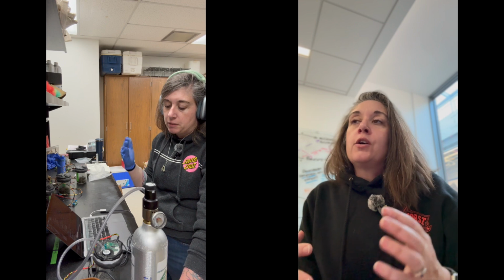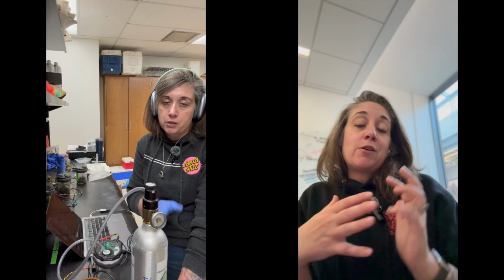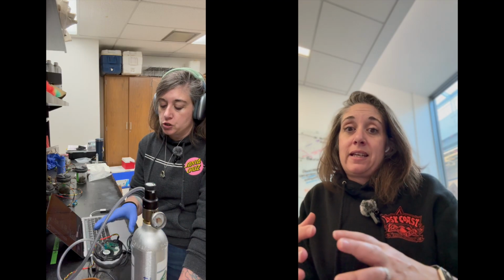So I will fill up a jar with a calibration gas. I usually do it with multiple different concentrations of calibration gas, because your leak rate is always going to be faster when the CO2 concentration is higher in the jar than it is out of the jar. I'll fill up that jar, make sure that I get it to or close to the calibration standard, and then I will let that sit overnight and see if the concentration decreases in the jar. Then I will do it again with a higher concentration calibration gas and see again if that happens.